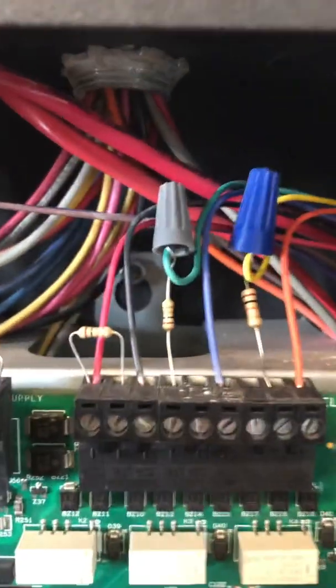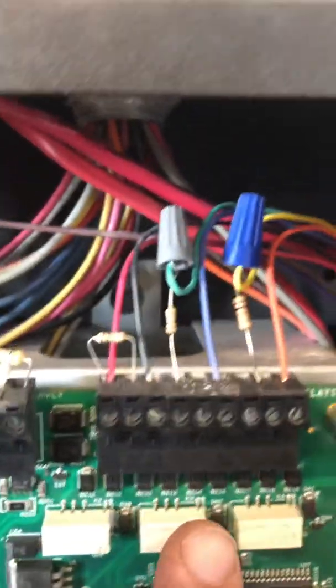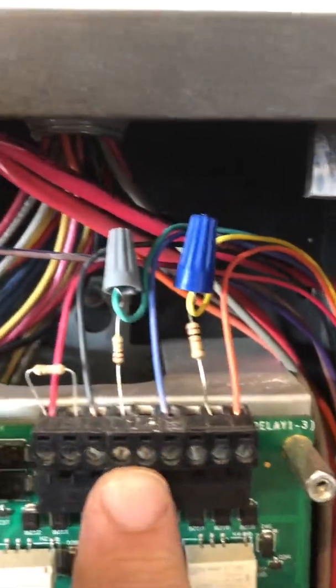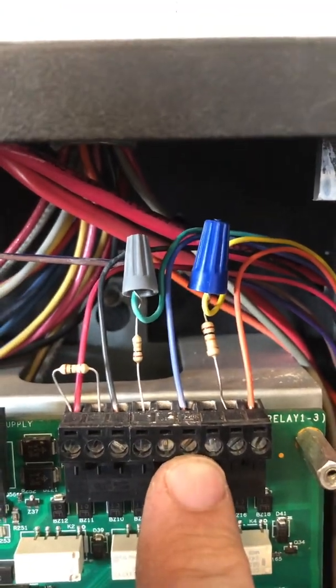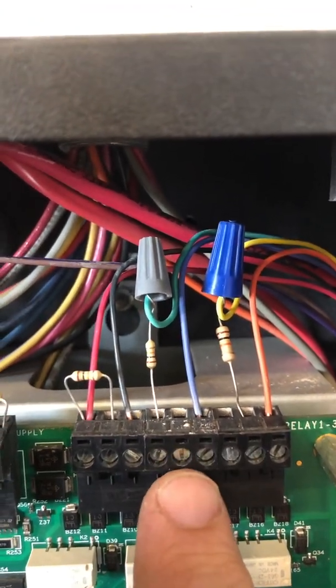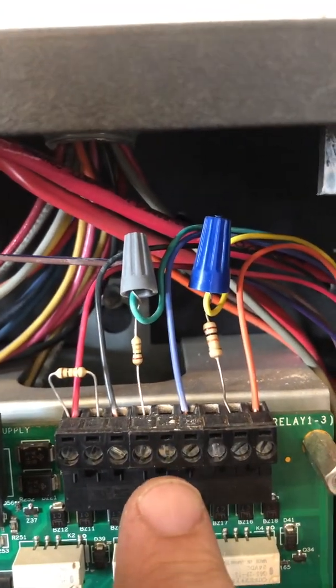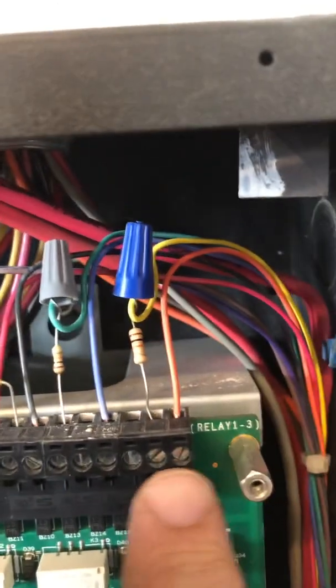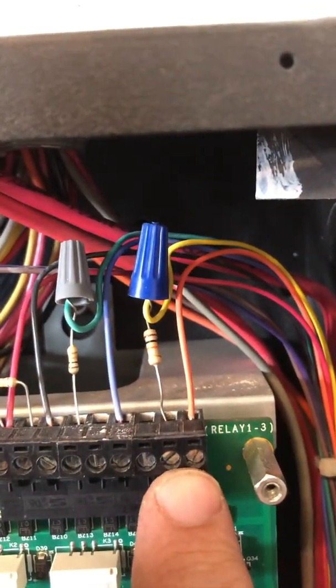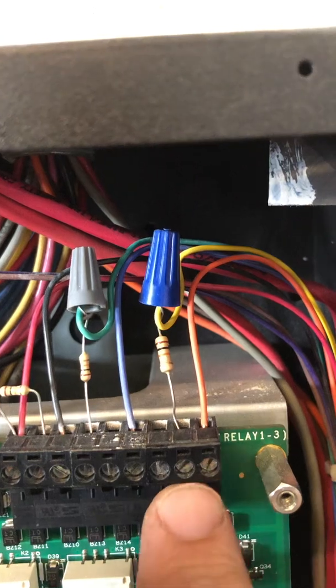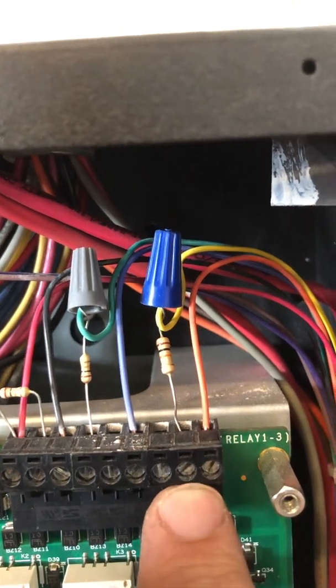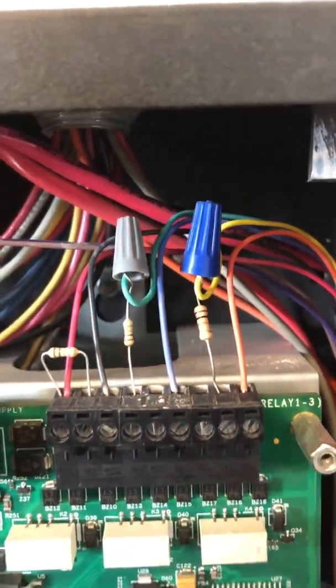The trouble is on the normally closed. It goes from normally closed to common. When we pull this off or when the panel goes into trouble, this circuit opens and sends a trouble up to the radio. Same thing with supervisory - they've got the common and normally closed on the right hand side in this case.